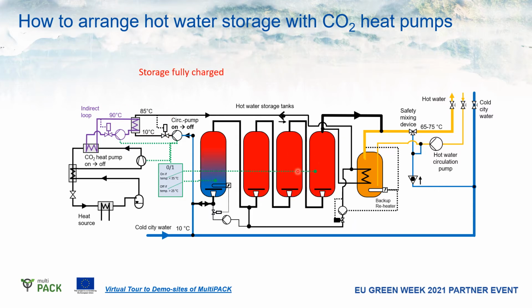After a while, you see that the tanks are fully charged, and this is detected by some temperature sensors, and in this case the heat pump will switch off, because the tank is fully charged. The return temperature of the water coming to the heat pump is increasing and the heat pump stops. However, the circulation in the building is continuously 24/7. In case there is not much hot water demand, the situation in the storage tanks will not change. However, the heat loss in these pipes circulating the hot water is continuously in place. So we need to find a measure to reheat the circulated water to achieve sufficient supply temperature.